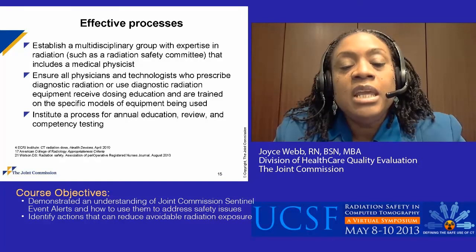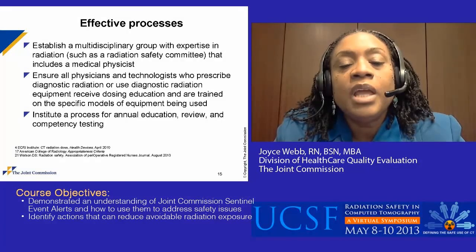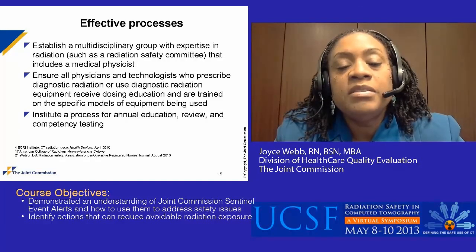Slide 15 provides more information for organizations and more guidance about establishing effective processes, making sure that there is a multidisciplinary group in place providing some oversight, and that group should include a medical physicist, ensuring that all physicians and technologists who prescribe and provide diagnostic radiation or operate that equipment receive education and are sufficiently trained on the procedures, and a process for ongoing annual education review and competency testing.